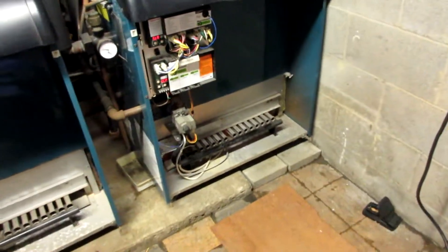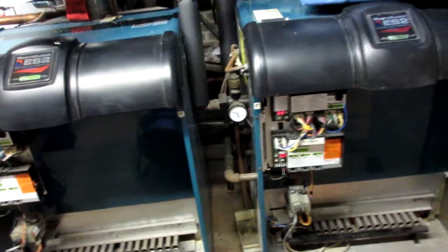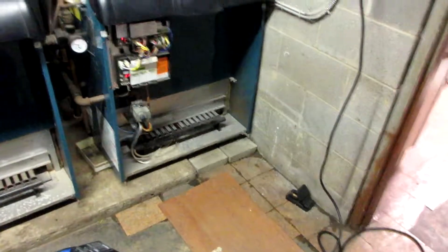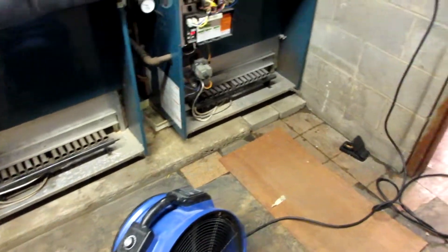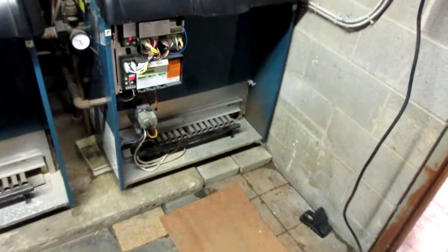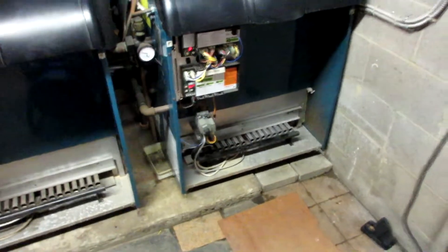The instructions say it tries to start six times. On the third try it lit and stayed lit. Technically only one of these boilers is needed for the whole building — it runs hot water through circulation pumps throughout the whole building. One of them is a backup. So right now everyone is going to start getting radiant heat.